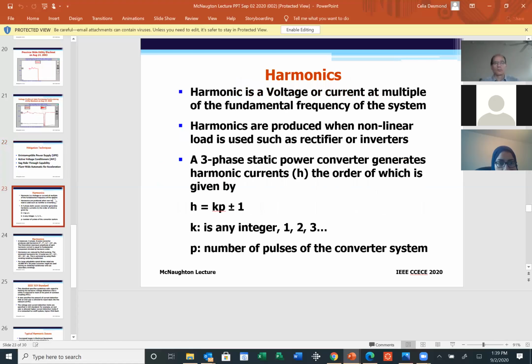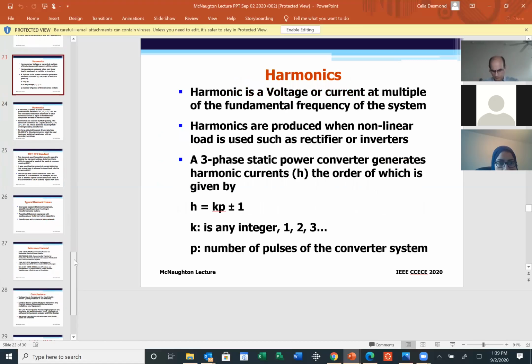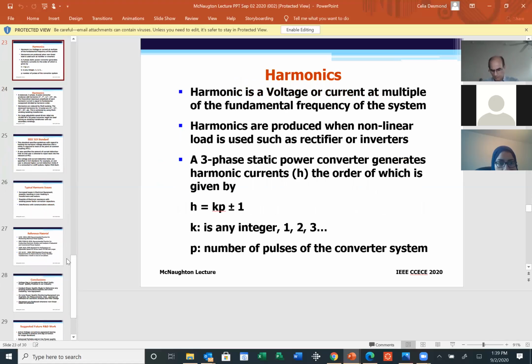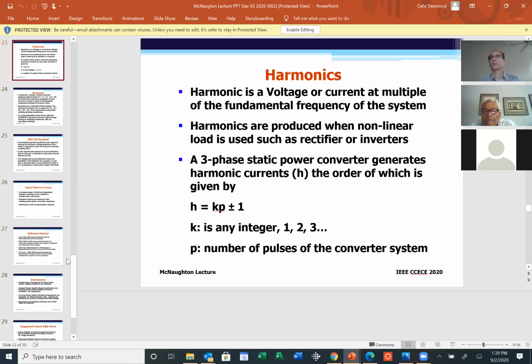Next slide, please. Now, the second issue I move on to is harmonics. This is a subject that I first faced when I was doing my PhD work, from 74 to 78, and it's still around to date. Harmonics is a voltage or a current at a multiple of the fundamental frequency. In simple language, you really like to see a sine wave in your system. Anything that departs from that, any non-sinusoidal waveform, has harmonics. For example, a square waveform will have harmonics. Typically, three-phase static power converters are widely used in industry, and they produce what we call odd harmonics. Next slide, please.